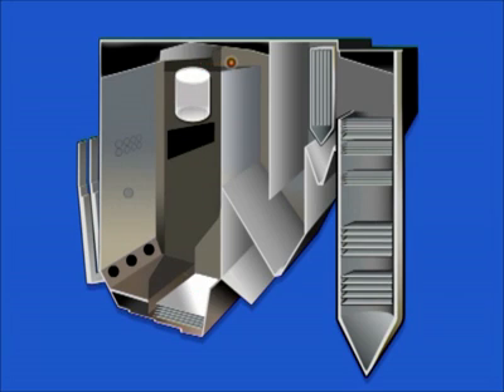The body of the furnace and separator are made up of tubes in which the boiler water is evaporated by the heat from the combustion. The hot flue gases are further cooled down in the idling duct before they continue to the superheater pack, where the steam is heated up to 60 bars and 480 degrees Celsius. The clinker is fed out from the base of the boiler and conveyed to a clinker bunker.